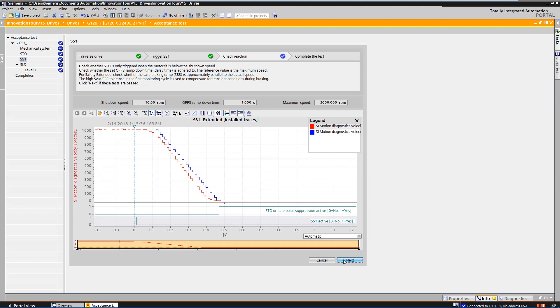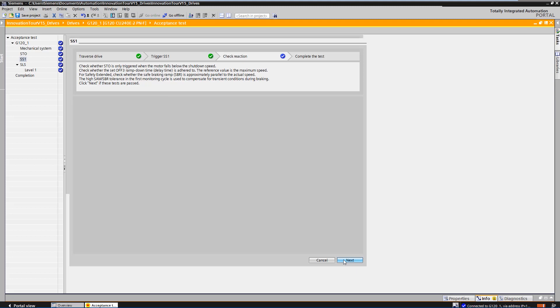During the braking process, Safe Stop 1 was active and after ramping down, the drive changed to Safe Torque Off. In addition, the drive was decelerated at the right time. So the trace is okay and everything looks fine.